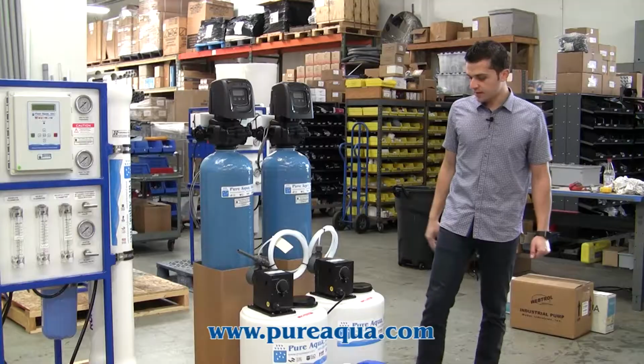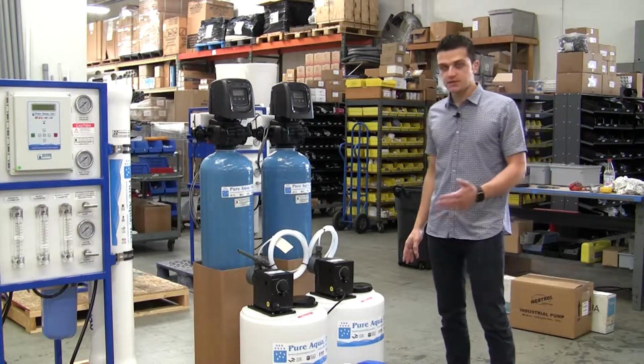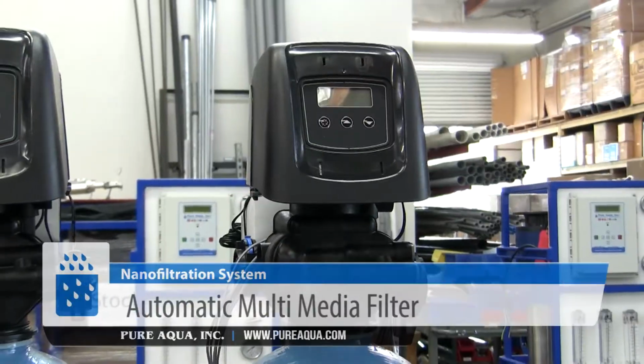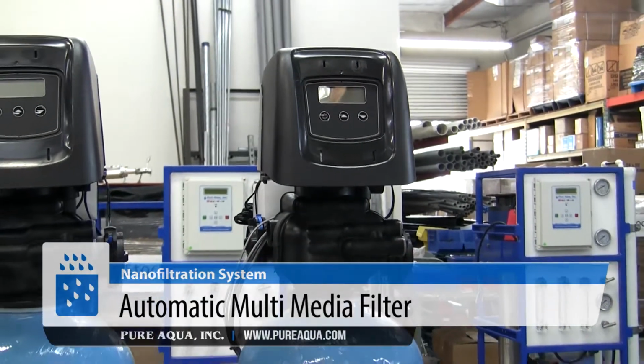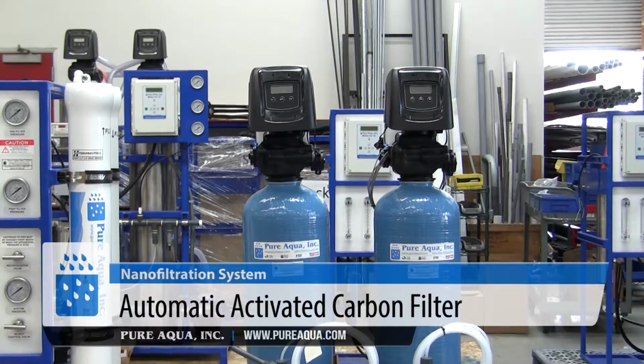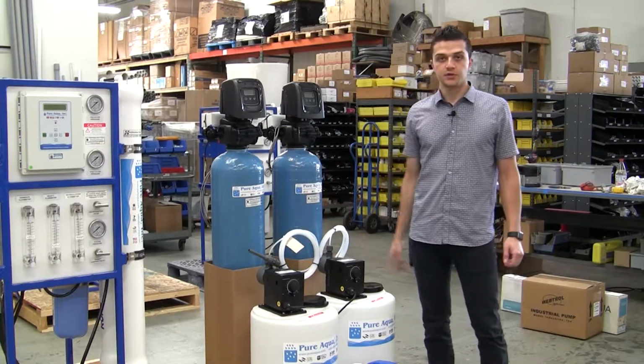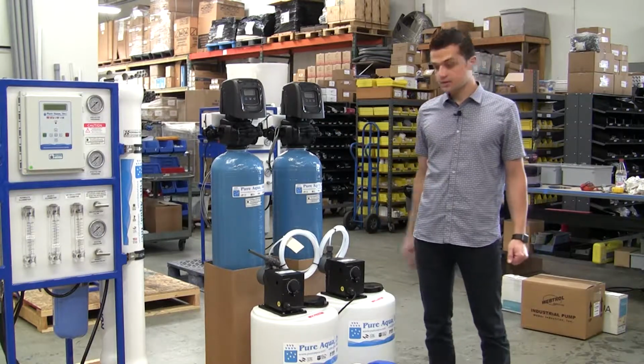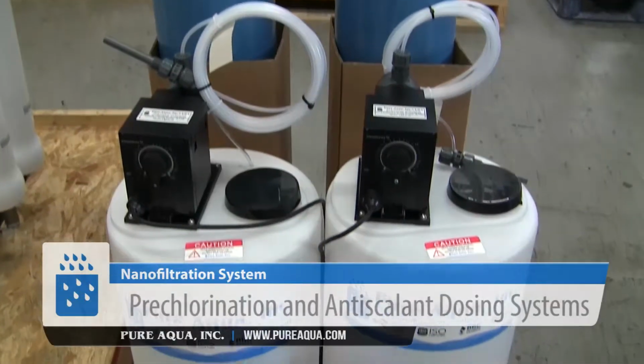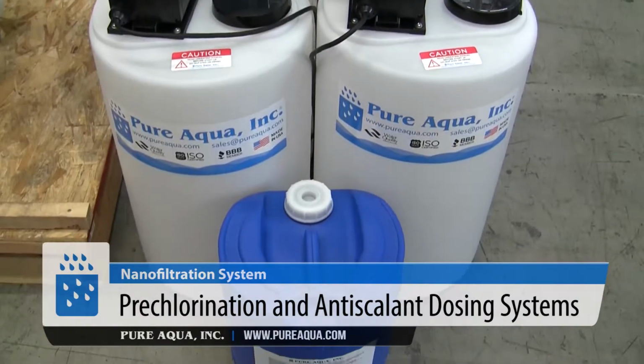So as part of the pre-treatment package, we've included a prechlorination dosing to help oxidize light metals and disinfect the feed water, followed by a multimedia filter to help reduce the turbidity. From there, we pass the water onto a carbon filter. The carbon filter helps remove any residual chlorine and reduce the organics in the water before feeding it to the membranes.